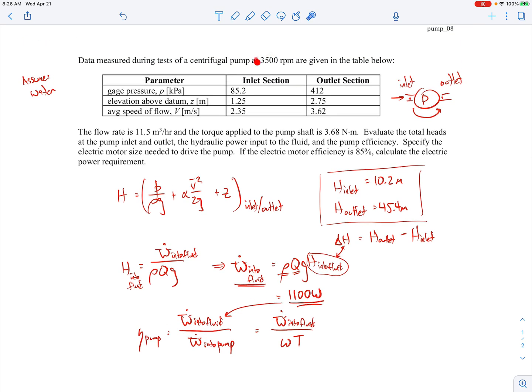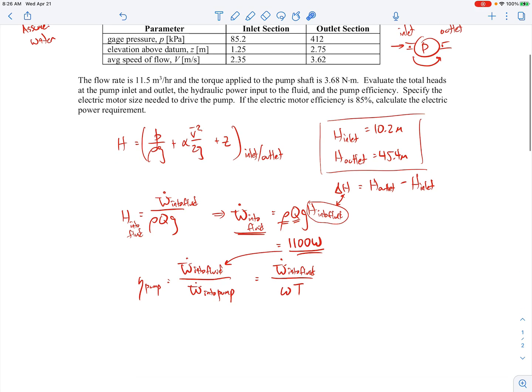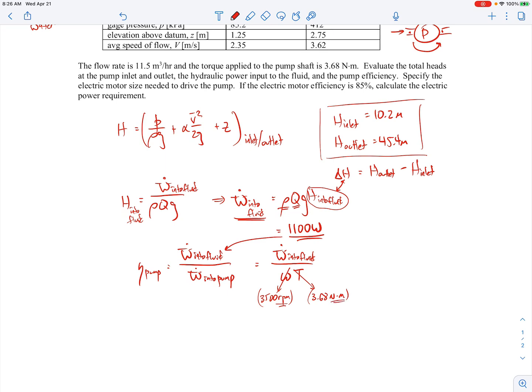The rotational speed is given as 3,500 RPM. There's a unit conversion required — you can't just multiply RPM by Newton-meters to get watts. You have to convert RPM to radians per second first, then multiply through. When you do that, the pump efficiency comes out to be about 80%.